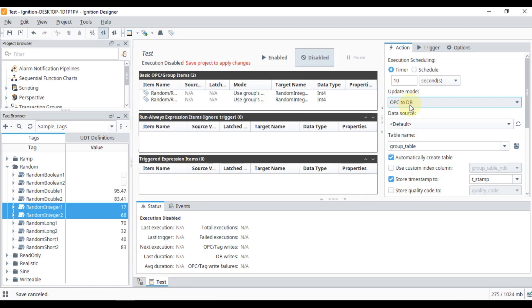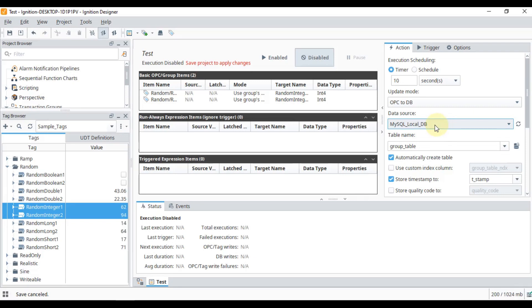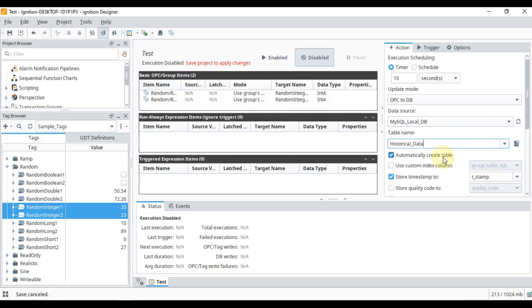You can see 'Update Mode' — this means I want to store my data from OPC to the database. For the data source, we will select the MySQL database we created in the previous video. We will set the table name to 'Historical_Data', enable automatic table creation if it doesn't exist, set custom index column to false, and store our timestamp in the 't_stamp' column.